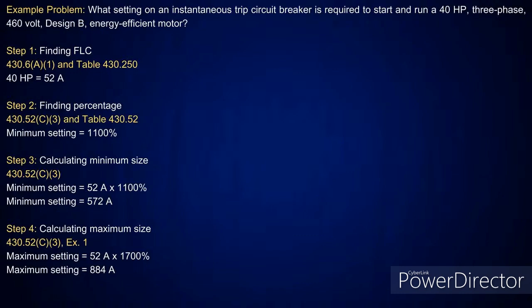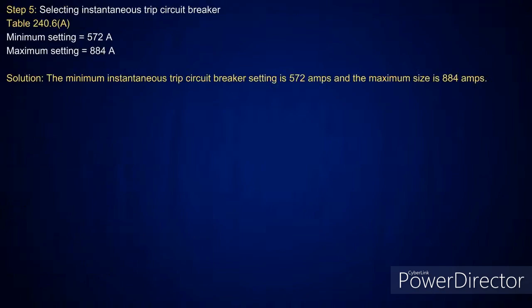If I look at Table 430.52 and pick up my Design B energy efficient motor, it's going to tell you take it at 1,100%. So I take the 52 amps at 1,100%, which gives me a minimum setting of 572 amps. Then I look at C3, and it says I can go up to a maximum of 1,700%, which is 884 amps. Okay. Right. Now, I do want to put that comment back up there.